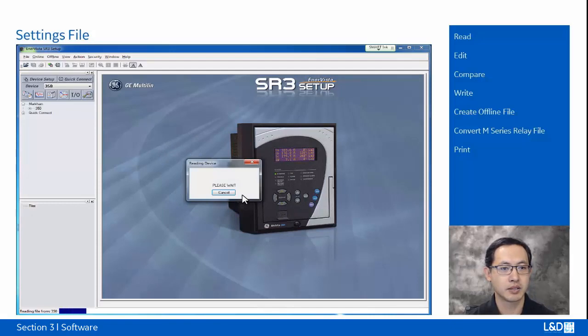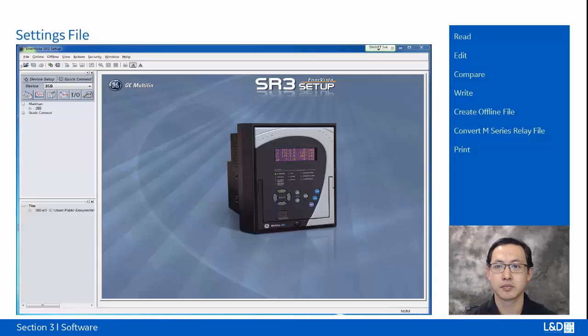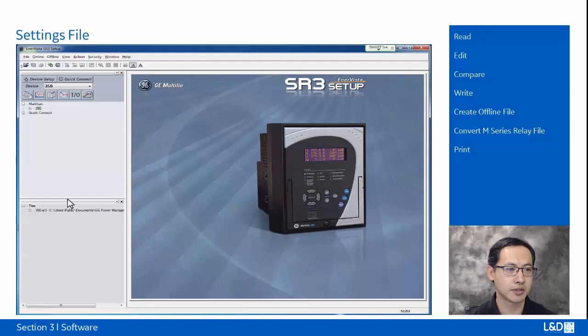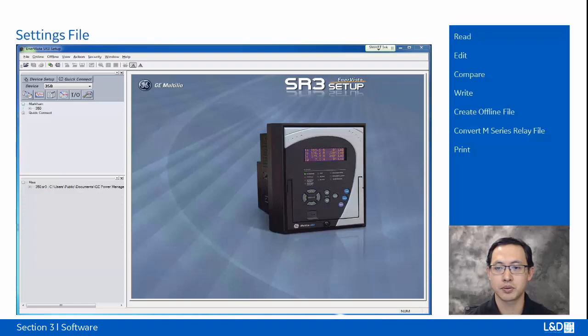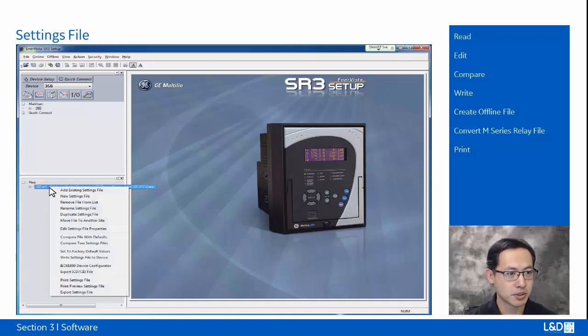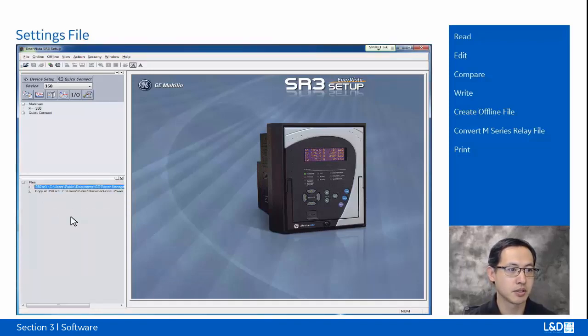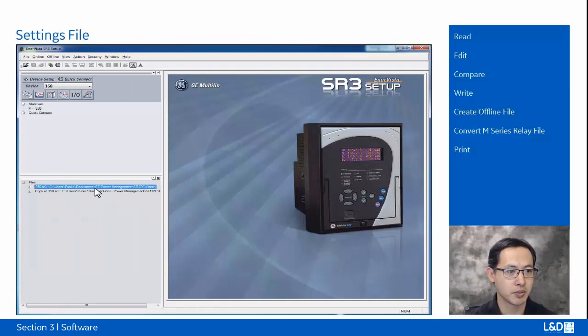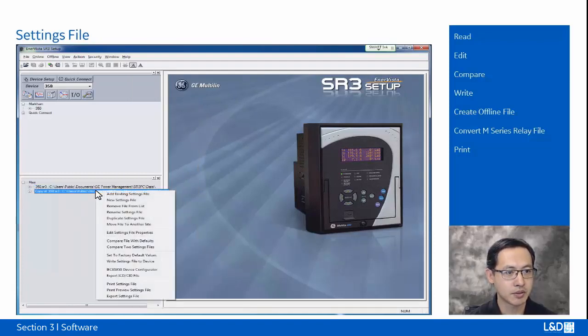And now we can see this setting file is being downloaded from the relay into the offline setting area. Once the download is finished, we have this offline setting file, and what we can do with this is duplicate the setting file. We can right-click the mouse and choose duplicate setting file. So on this copy, we can play with the editing of the setting file.